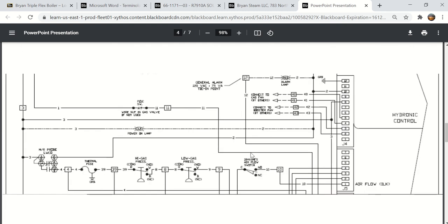So we'll scroll down to the next screenshot here, and then we get to this part here, MR probe LWCO. Okay, important to know exactly what this means and what it's telling you. MR stands for manual reset, probe LWCO. LWCO is low water cutoff, and it's a probe type low water cutoff.